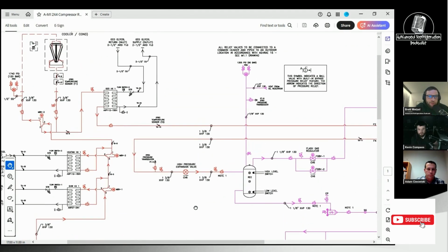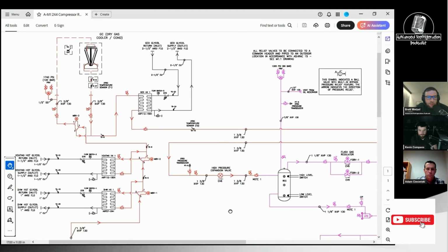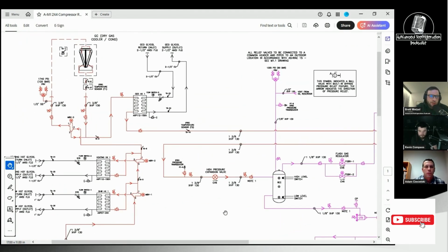Oh, this is making a lot more sense now that I'm actually seeing it. All right, so you have your hot glycol. So you're trying to heat the potable water first, then you're heating up the glycol for the heating loop. And then the next thing is any residual that you have, you're just dumping into that heat exchanger that goes into the basically the thermal wells that are in the ground, correct? Yeah.